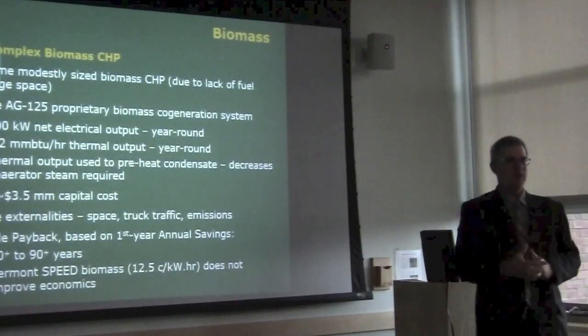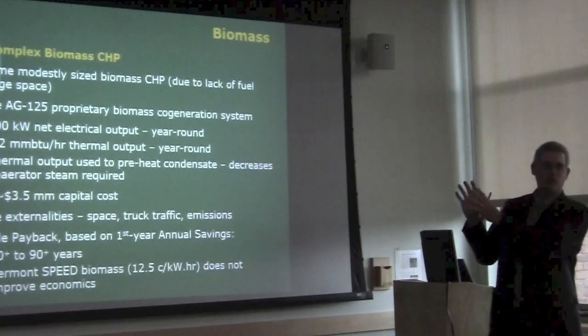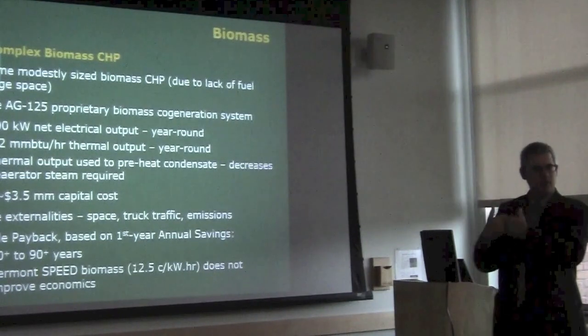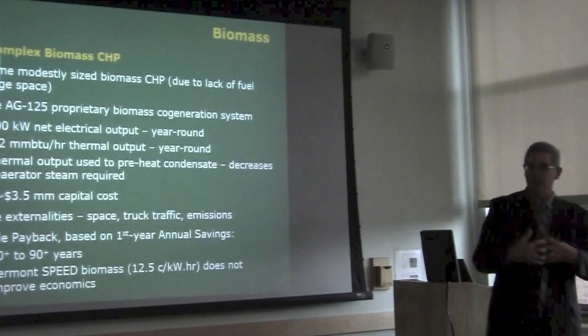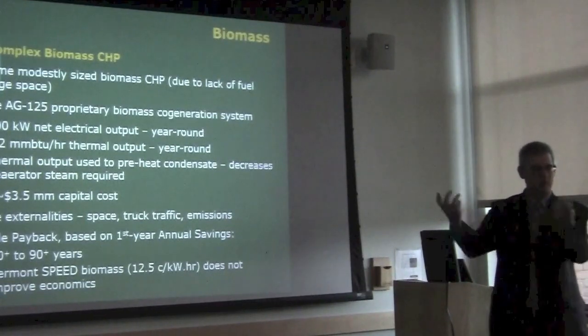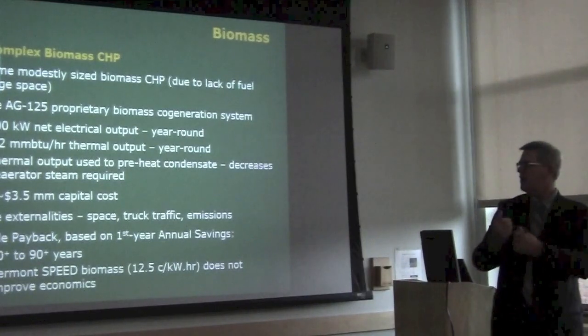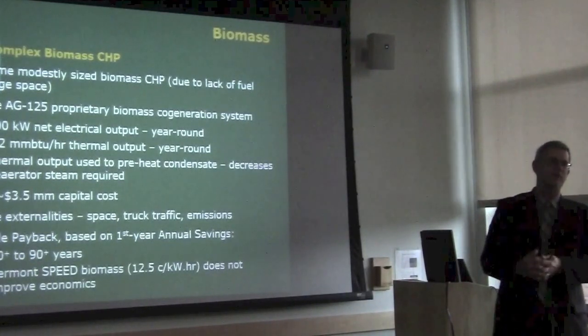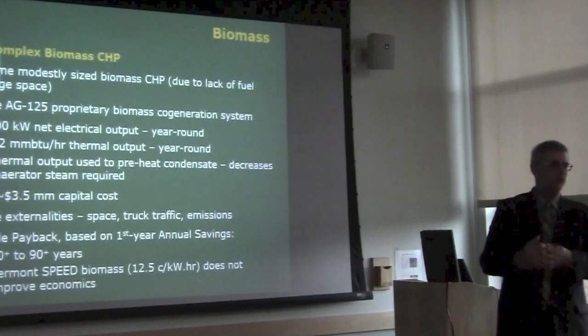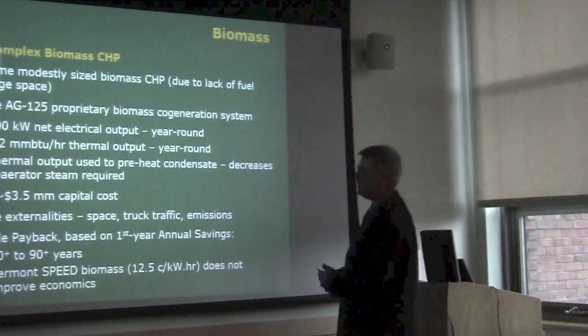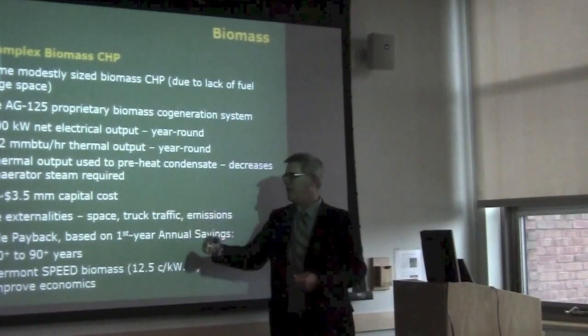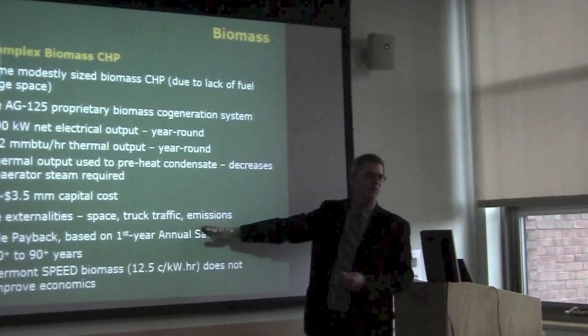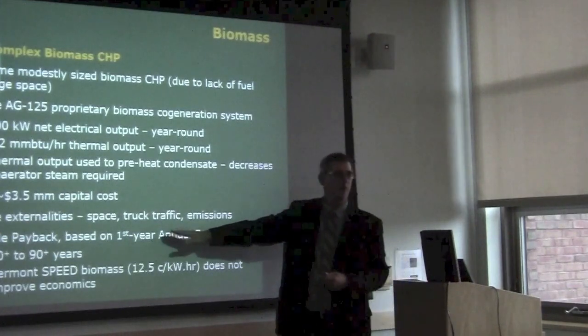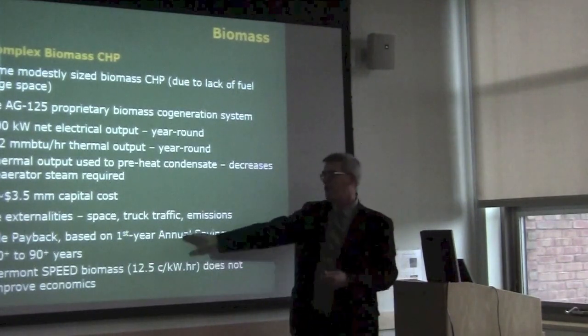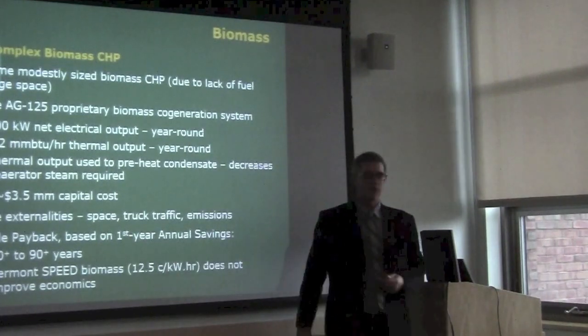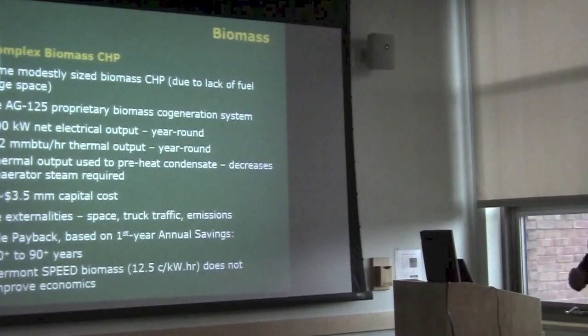Yes, so Matt, to answer your question, we took that same AG125 system we were talking about with Trinity, and we took it to the Cage complex. Instead of trying to make steam with it, we basically preheated the condensate coming back from all the various condensate lines, which decreases the deaerator or auxiliary steam consumption within the Cage plant itself. Not a lot, it's modest, but it is a gain basically. We did the same analysis; it's still basically in the $3 to $3.5 million range. We have the same externalities, other than the trucks are now driving into the middle of campus, and there's piles of wood near campus buildings. Simple payback, 20 to 90 years in this case. And again, the biomass standard offer price does not really improve those economics.